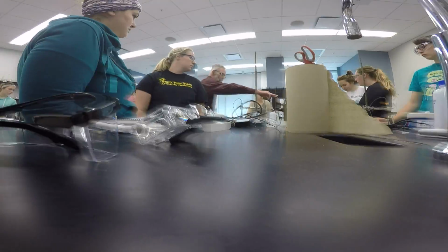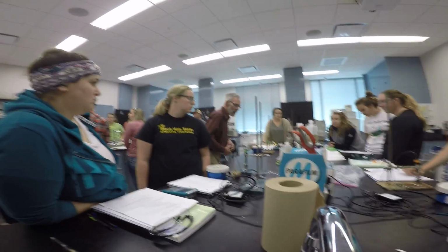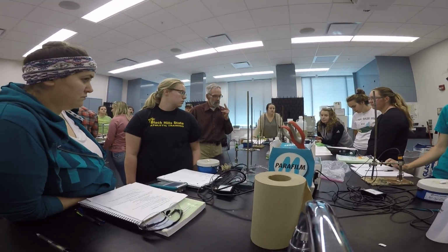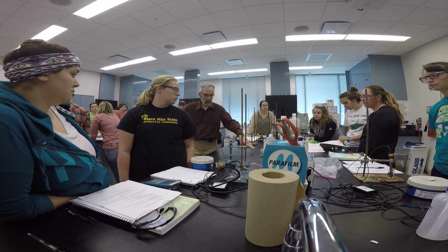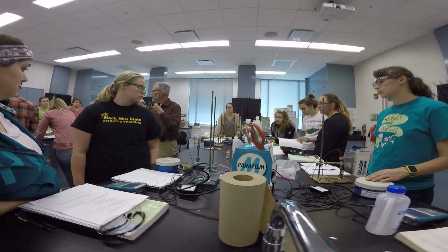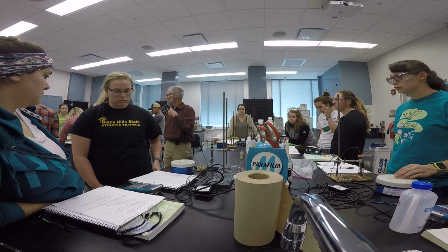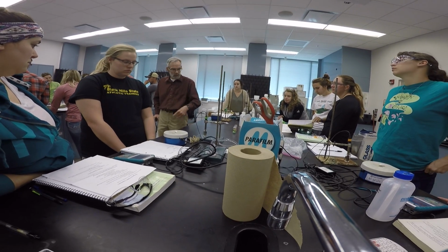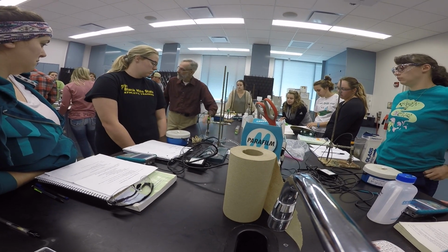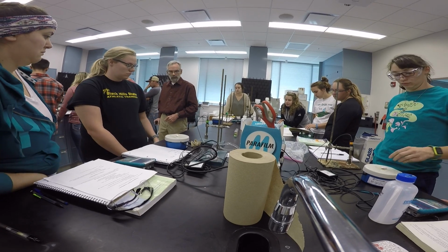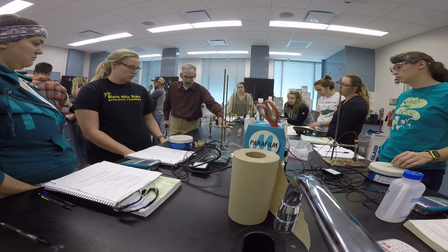One here, one there. And with those, you grab the 2 pH standards that are as close to the pH you're trying to measure as possible. So if you're trying to make a buffer at pH 3, you grab 4 and 7. Try to make a buffer at pH 11, you grab 7 and 10.